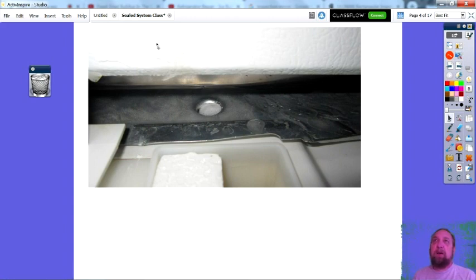This right above it is the evaporator. When it goes into defrost, any ice that melts runs into this pan. This pan is angled to force the water to here, and this drops into the refrigerator and then drops out the back to the compressor into a drain pan down below there. Now, if this is frozen, the water that drips will eventually run forward.